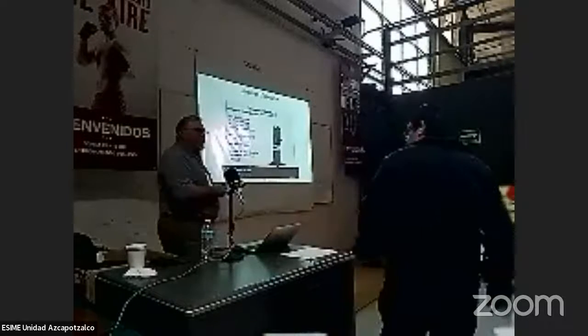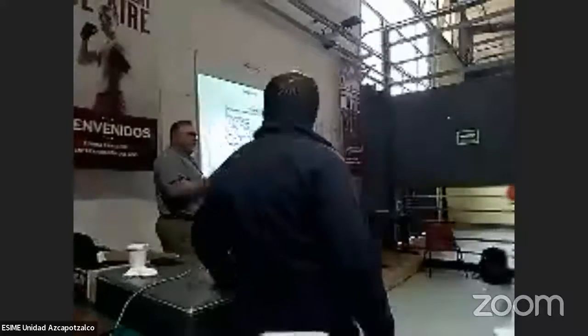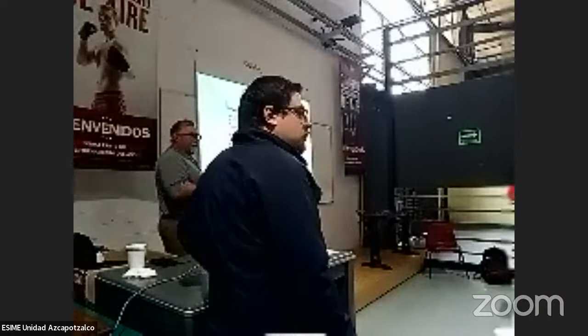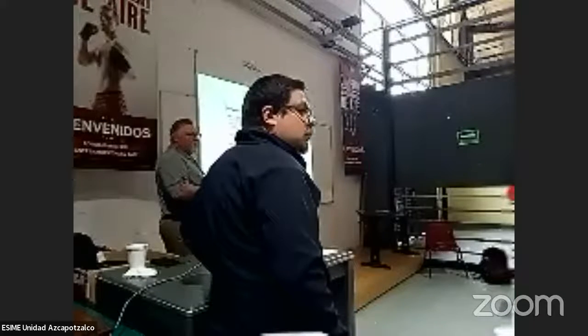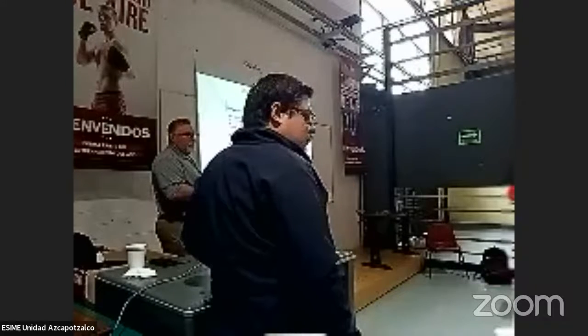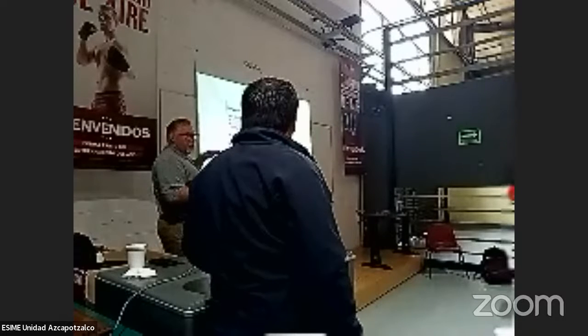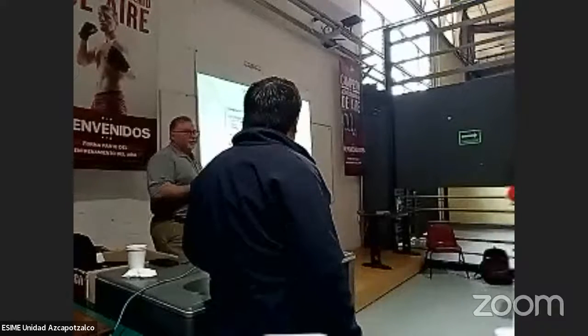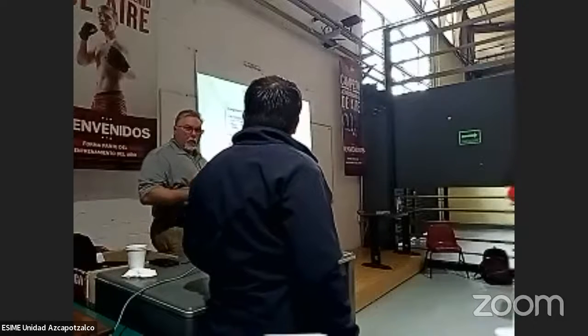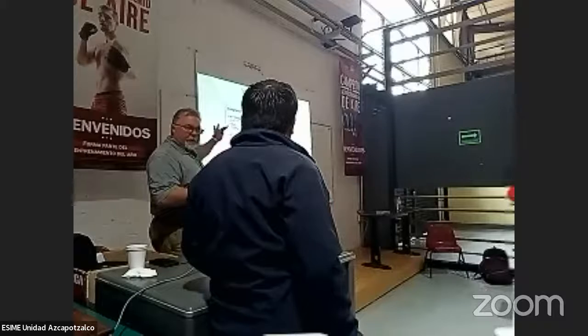Compressor blocking. I haven't taught this in a while. I don't remember what that's about. It's just saying that it's constantly listening to hold the compressor off until it gets above that. So it's just blocking unless those parameters are met. There's logic built into the board that will not allow the compressor to go on unless the parameters are met.